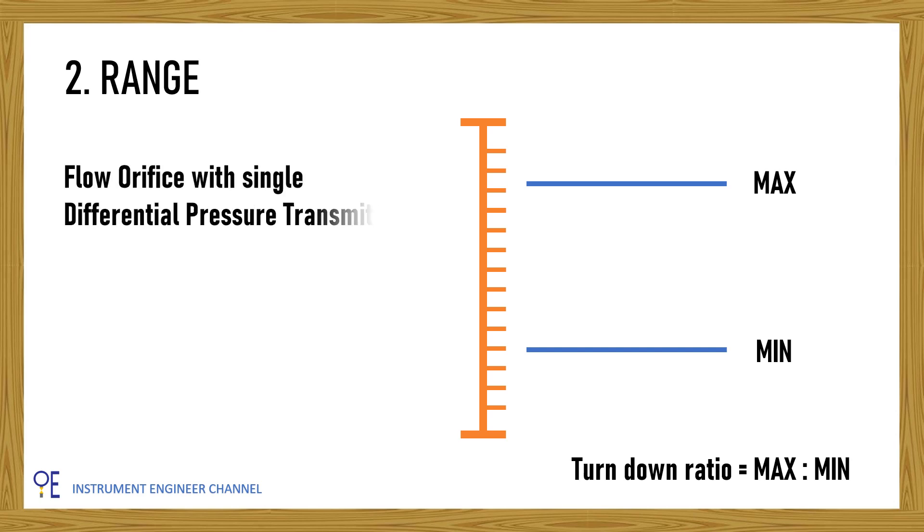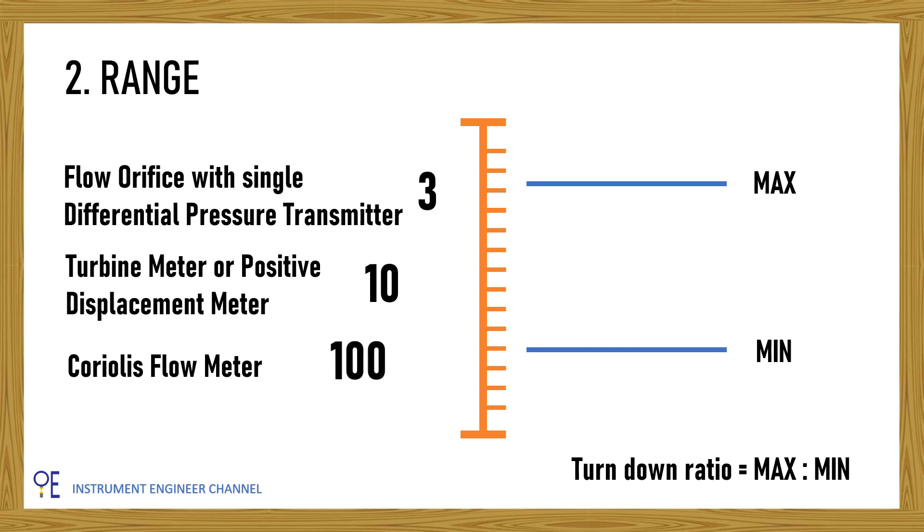Flow orifice with single differential pressure transmitter can only have turndown ratio 3. Common turbine meter or positive displacement meter have turndown ratio 10, while Coriolis can have turndown ratio up to 100 and ultrasonic flow meter even higher.